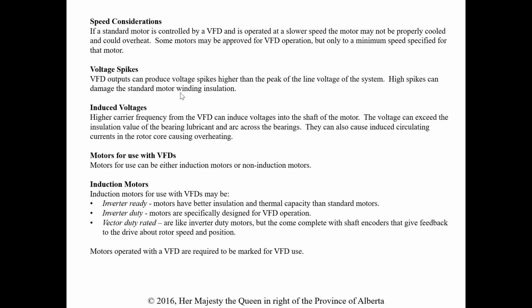Induced voltages: we can get higher carrier frequencies from the VFD, and they'll go into detail of all of these things coming up here, and that induces voltage into the shaft of the motor. This can exceed the insulation value of the bearing lubricant and arc across the bearing. So if they arc, they could get welded together and then obviously not allow the motor to spin freely. We can also get circulating currents in the core causing overheating. Obviously overheating is damage and we want to avoid that as well.